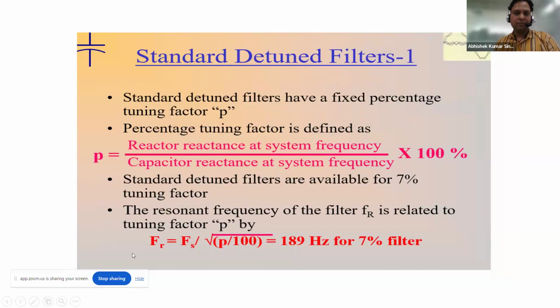Here we can see that this is FR, and this is FS. FS is the system frequency, and this is the tuning factor. If you divide the 50 hertz by this p, meaning 7 or 14, whatever it is, it is 189 hertz. That means whatever frequency is above 189 hertz, it will block all of those frequencies, but it will not block below 189.